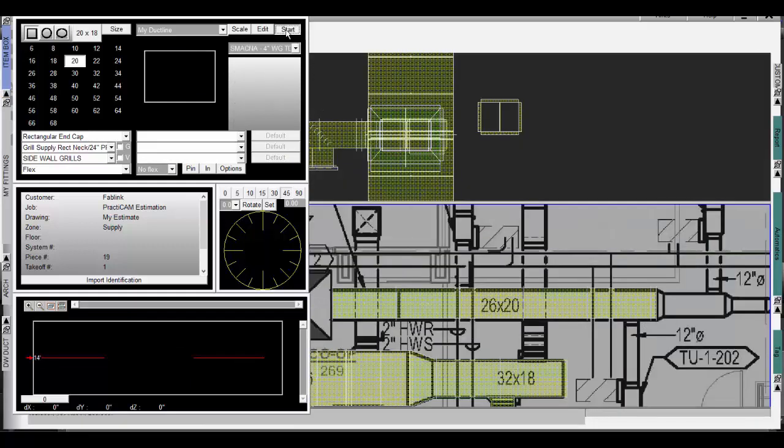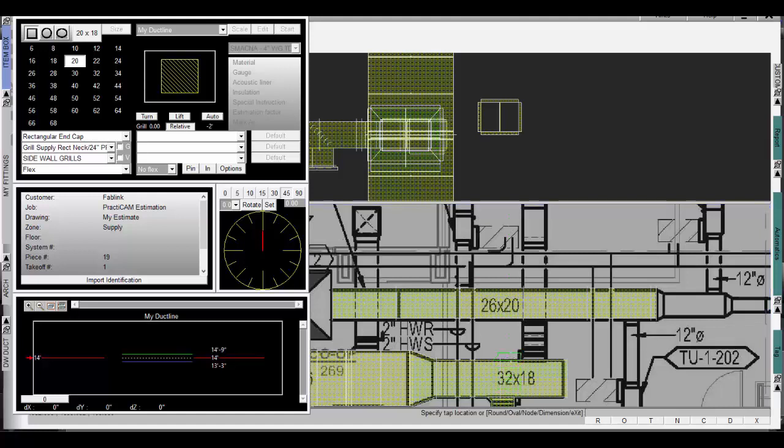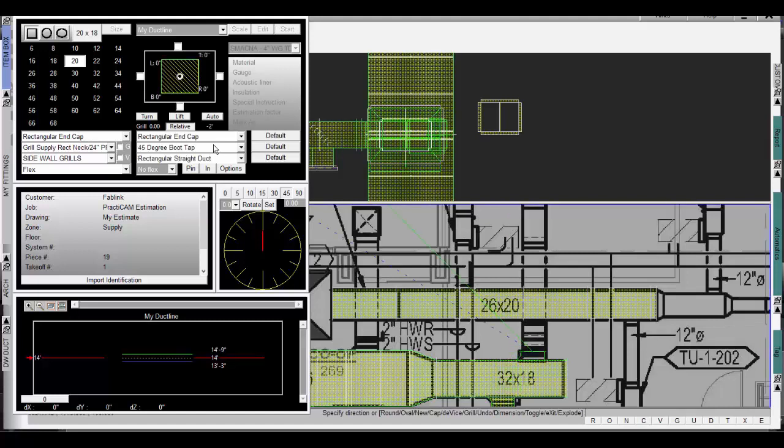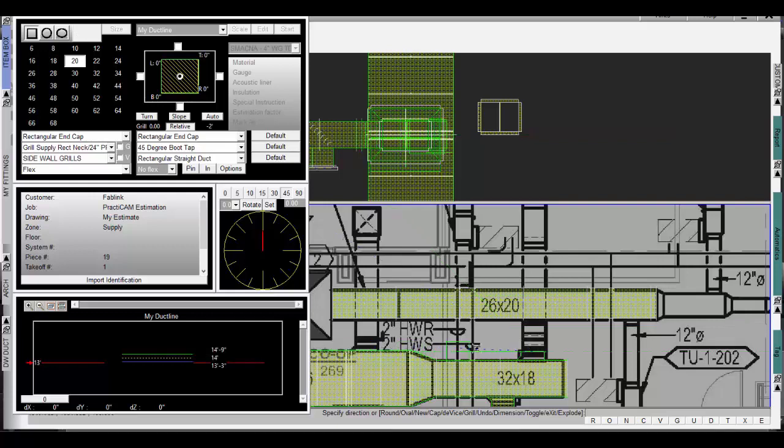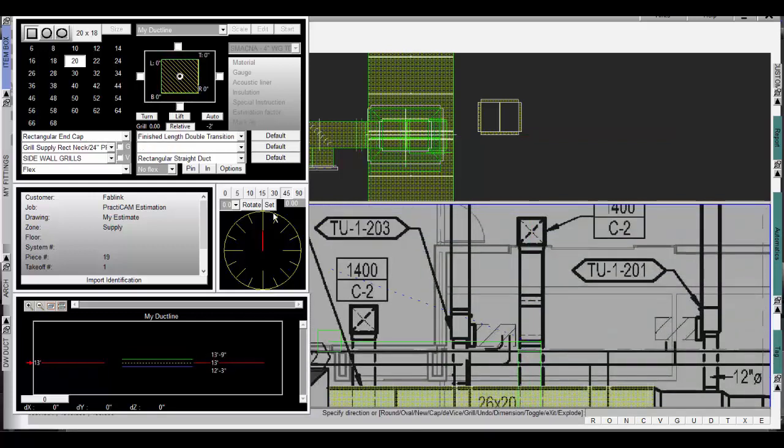Notice these risers are perfectly drawn between our two points and with whatever manufacturing specifications we chose. Next we will demonstrate drawing on a slope. See here as we touch the Ductline to get an automatic boot tap to form. Then we use the slope 2 command to pick the point we want the duct to slope down to, draw under the collisions we are trying to avoid, and then use the slope 2 again to get back to our original height.